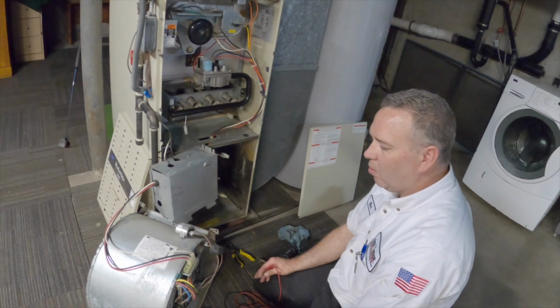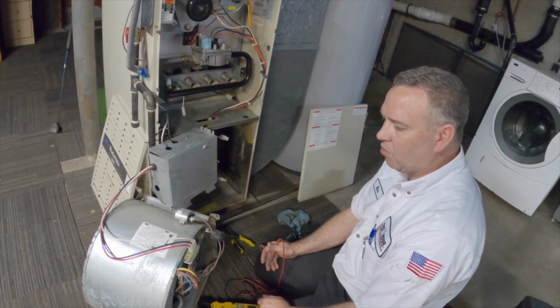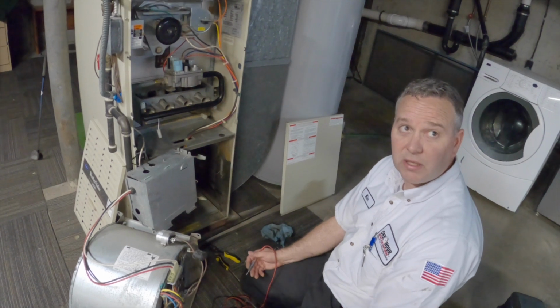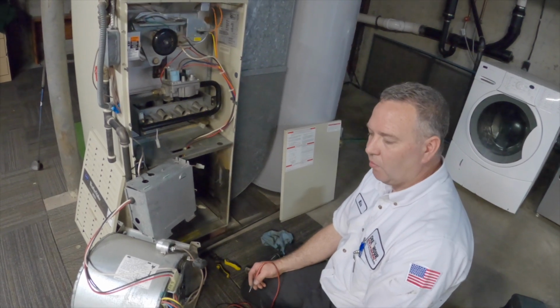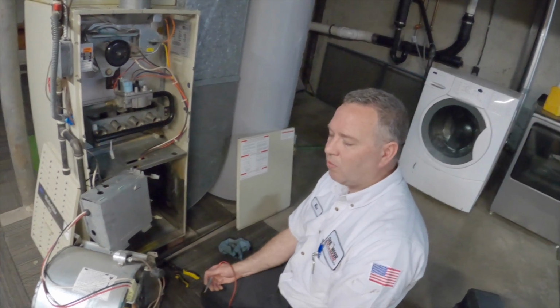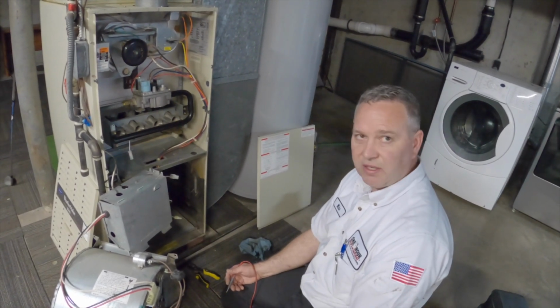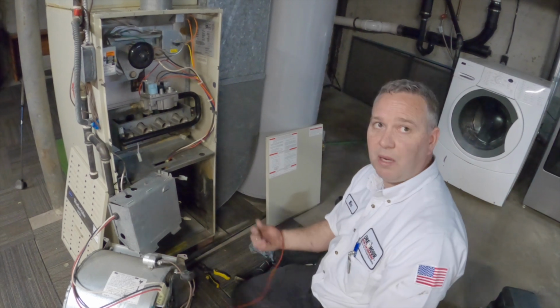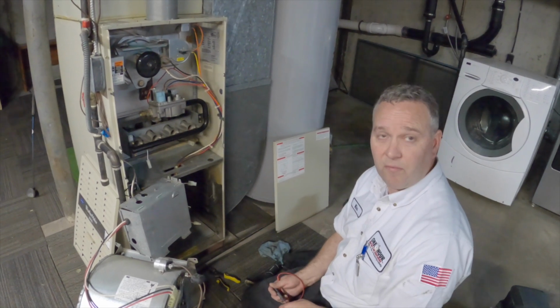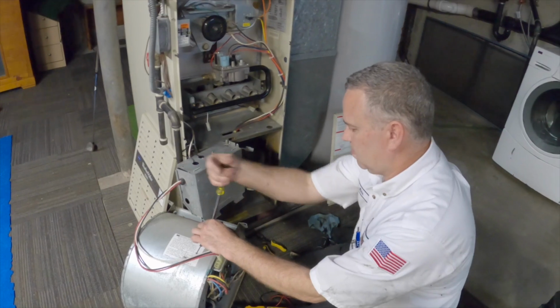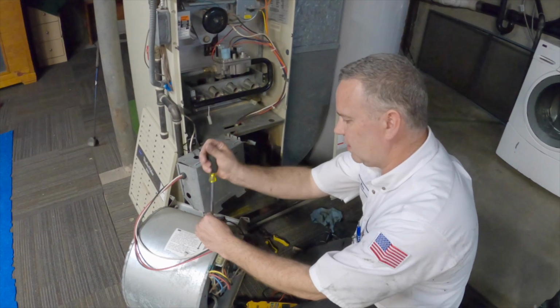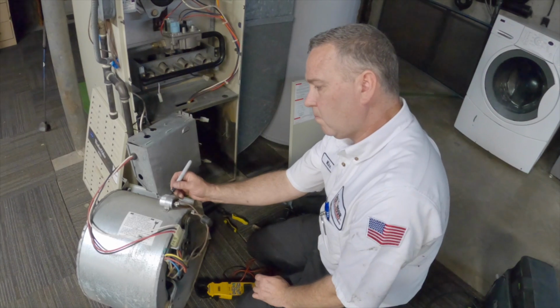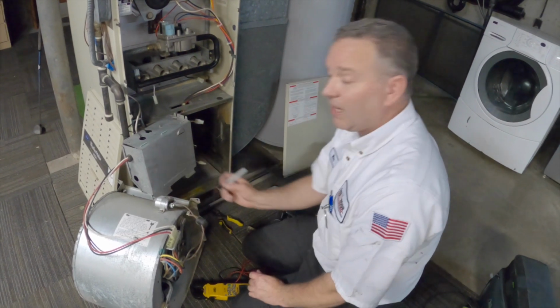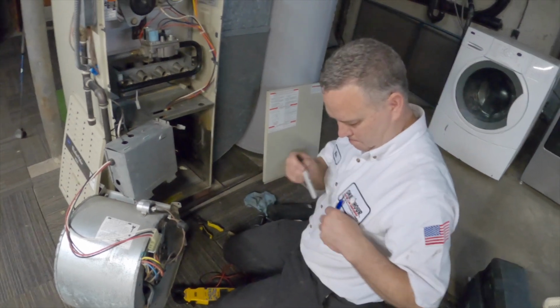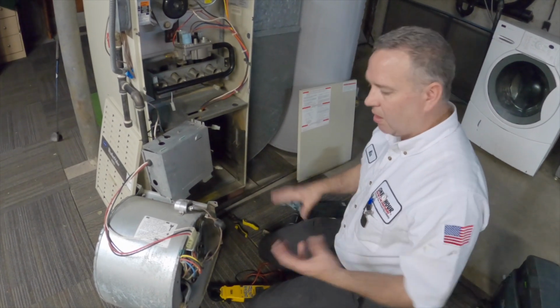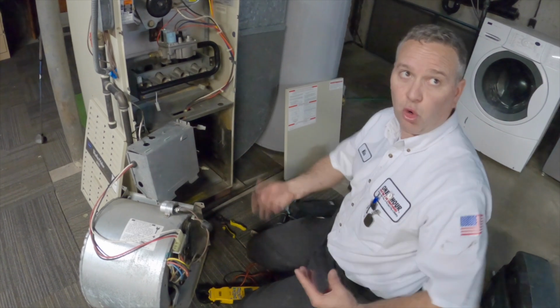When it gets low, the manufacturer recommends replacement typically after it gets 5% low or 6%. We as an industry recommend once it gets to 10% low, that's when you replace it. I'm just making sure that it's within the design specifications, because if it's not, then it's making that motor work harder, in turn can make that motor fail faster than it's supposed to. You never can see what size it is. You have to take things apart to make sure that the capacitor is not failing, that could save your motor. Exactly. If you stay on top of the capacitor, less wear and tear on that motor. It's not working as hard when the battery's essentially charged like it's supposed to be.